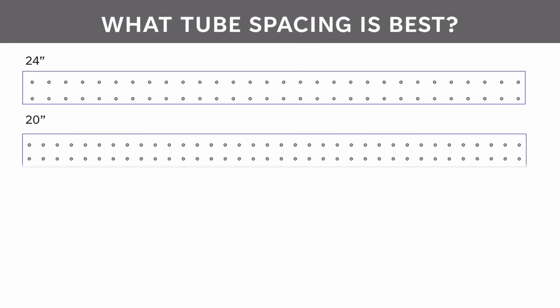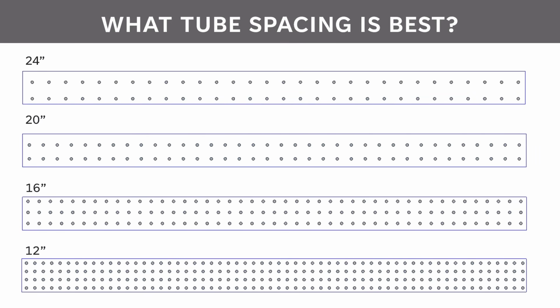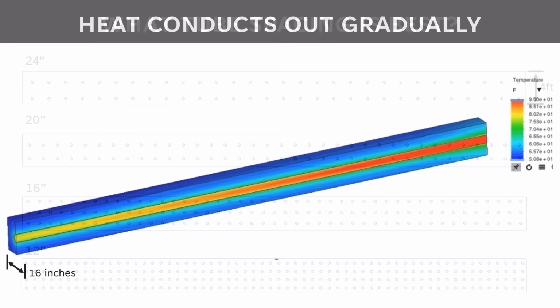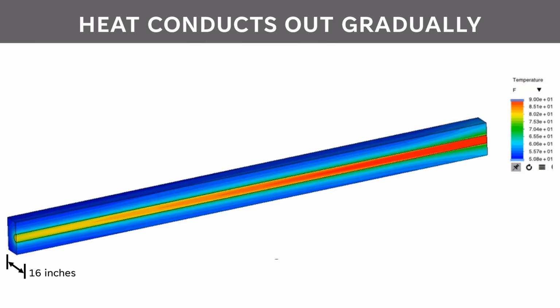Let's look at an end view of a few options to see what a range of tube spacings would look like. All of these layouts are to scale and assume a 4-foot depth. Seeing the number of tubes, it quickly becomes clear that this is a very important and a potentially costly decision. Let's step back to the numerical simulation for a quick refresher. We see that the temperature of the soil is highest in contact with the tube, and it decreases with distance from the tube. Now, let's look at the system from the side, or end view.